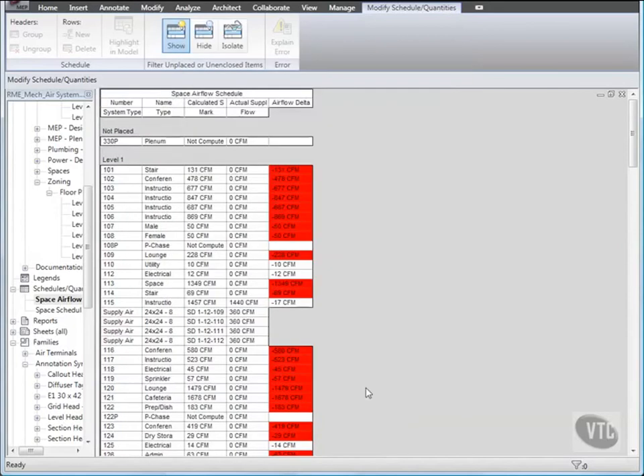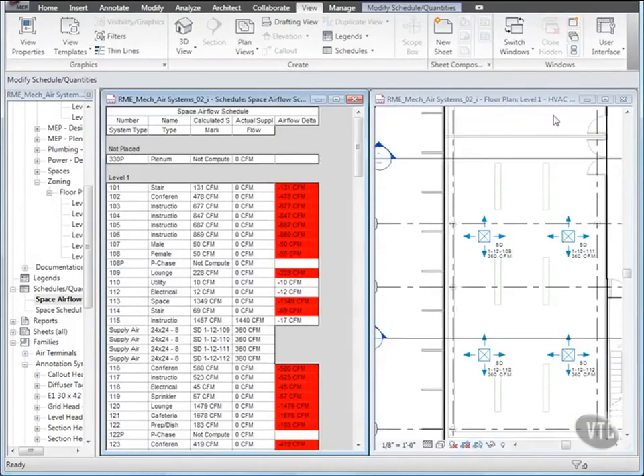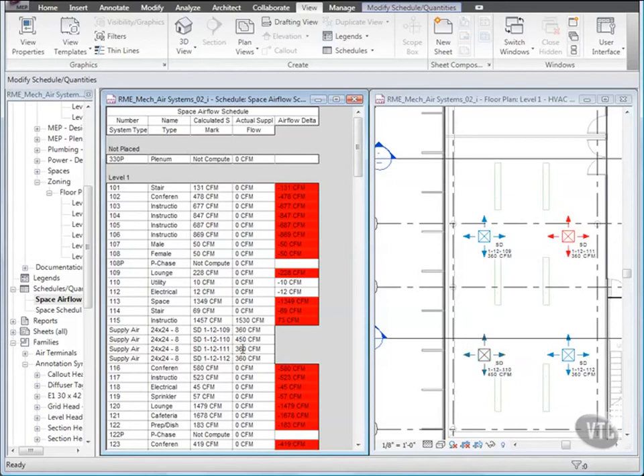Next, let's modify an Airflow Value in the Schedule. Tile the windows again. Then in the Schedule, under Space 115, select SD 1-12-109, and change the Flow to 450 CFM. Then using the same method, change the Flow for 111 and 112 to 330. Now the Airflow Delta Value for the Space updates to a positive number.